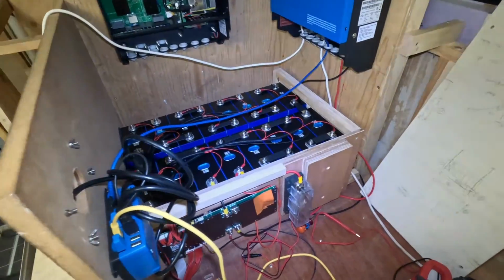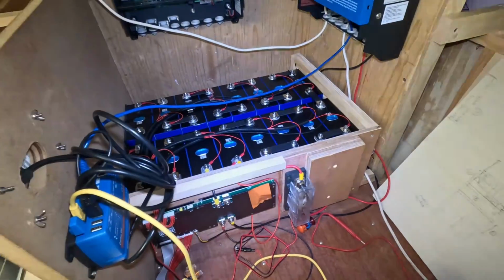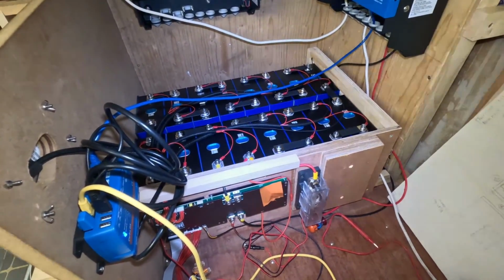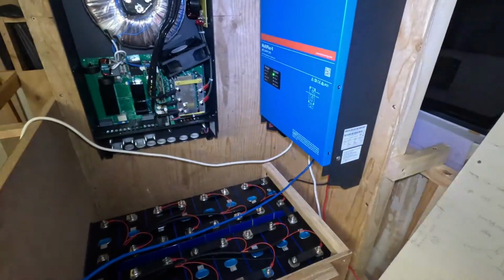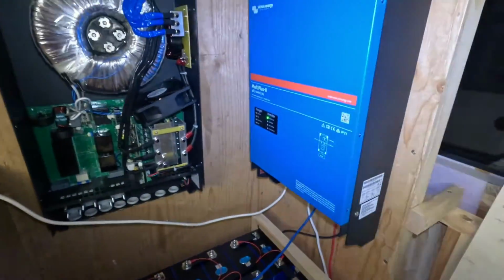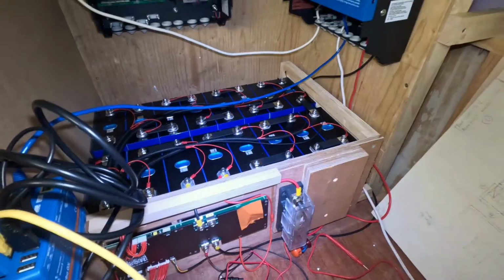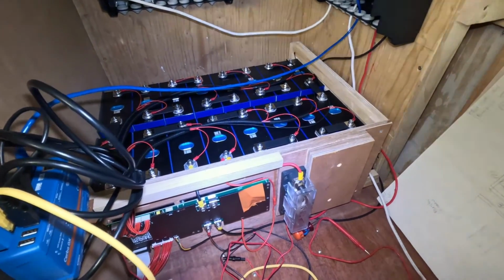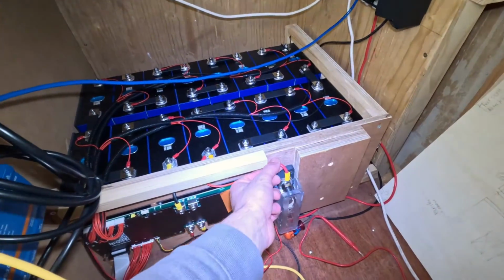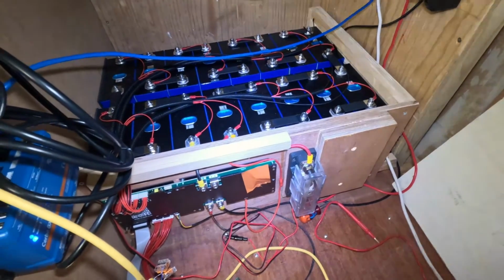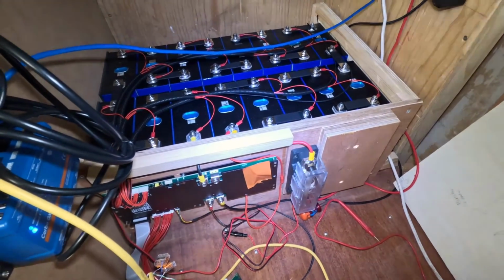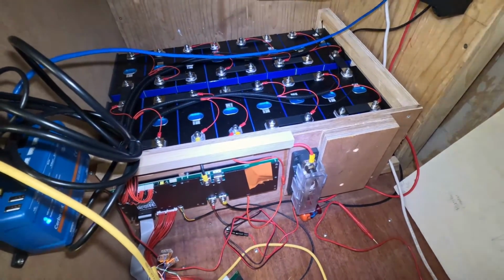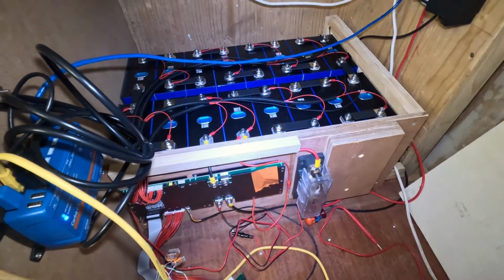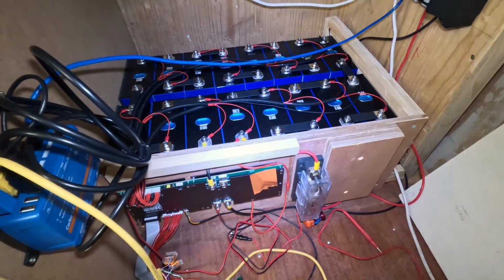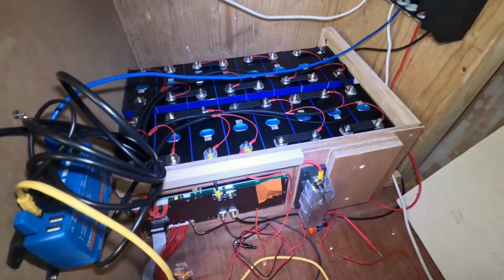Okay, so the battery pack is now hooked up together. I've also very quick and dirty hooked up one of the multipluses, and not with the proper cabling or anything at all. I just use this, as you can see, thin 6 square millimeter cable. It's definitely way too small, but it was the only thing that I had available, and I really wanted to start to do the first charge of this battery pack.